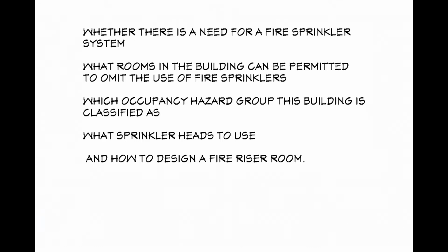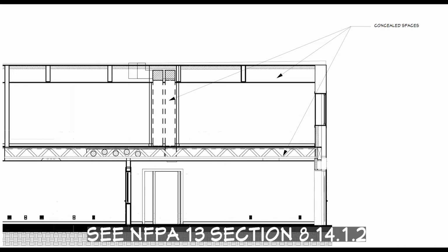Automatic sprinkler systems are oftentimes necessary to protect the building from burning down and to save the lives of the building occupants. In order for a sprinkler system to achieve these goals, designers have to assess the potential of ignition in each space. According to NFPA 13, all newly constructed commercial buildings that are 5,000 square feet or larger are required to have sprinkler systems. However, sprinkler systems can be omitted in spaces that are unlikely to ignite or if the sprinkler installation may not be practical based on the building geometry. This typically applies for concealed spaces that aren't built out of combustible materials. Concealed spaces in commercial buildings larger than 5,000 square feet should be sprinklered unless the local authority allows them to be omitted. Buildings or parts of buildings are assessed for potential of ignition based on their occupancy hazard classification.